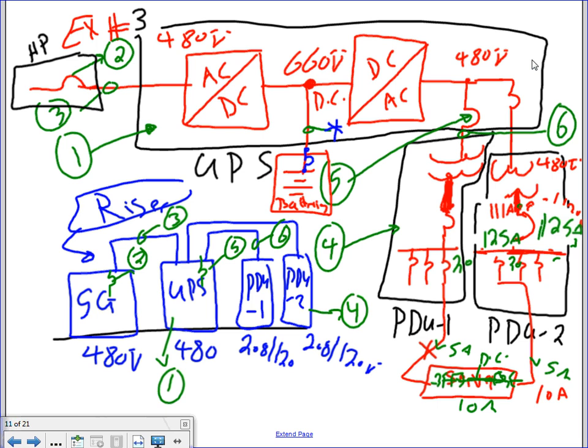Okay, I want to remind you that PDUs are 208 because there is a transformer inside them. The UPS is 480 because there is no transformer inside it. It takes 480 here, converts it to DC, and inverts it back at 480. So you have a 480 system, 480 DC, 660 volt, 480. Up to this point, it's 480. Inside the PDUs, it converts it to 208. Now we're at 208 here, and we distribute it at 208, 120, 208 across these servers. And some of them are fed, guys, 208. Some of them are fed directly from two hots. Some of them are 120.